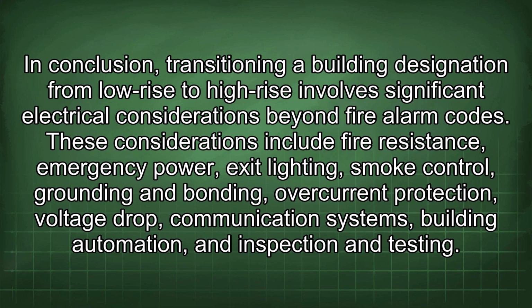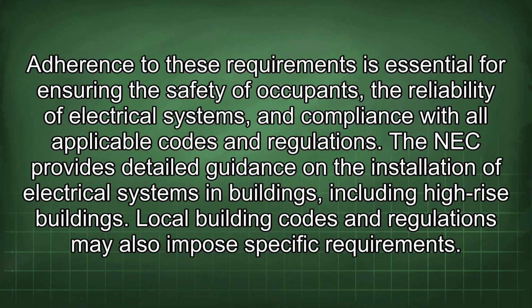In conclusion, transitioning a building designation from low-rise to high-rise involves significant electrical considerations beyond fire alarm codes. These considerations include fire resistance, emergency power, exit lighting, smoke control, grounding and bonding, overcurrent protection, voltage drop, communication systems, building automation, and inspection and testing. Adherence to these requirements is essential for ensuring the safety of occupants, the reliability of electrical systems, and compliance with all applicable codes and regulations.